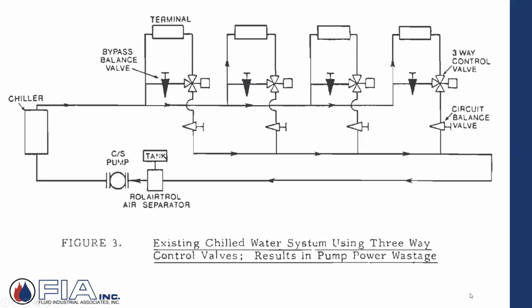Downside, you see it right here stated, and it's Mother Nature, it's a fact, pump power waste. It got you from that phenomenon of having this 2-way valve, seeing all this pressure drop because it's backing up on its curve. What's the purpose of these black bypass balance valves? Well, that can be, the piping itself is your bypass. You're absolutely right. And it's a bypass balance valve. And the question is, why is it needed?